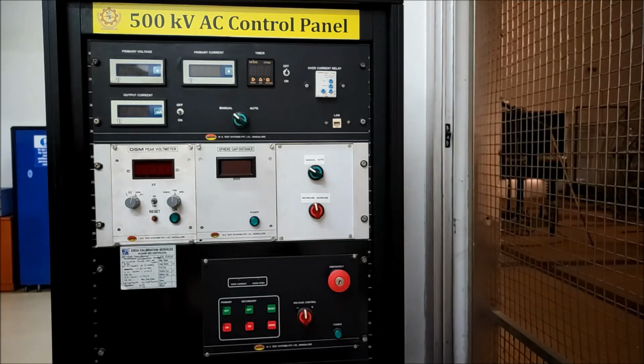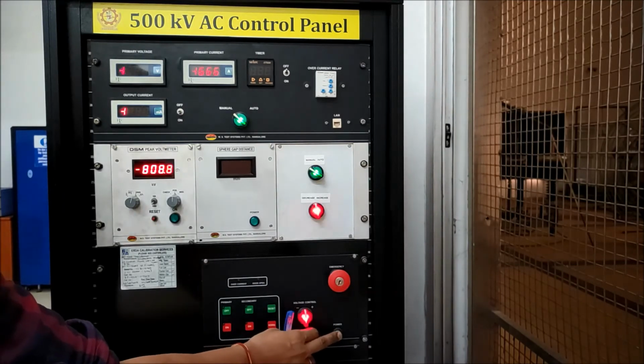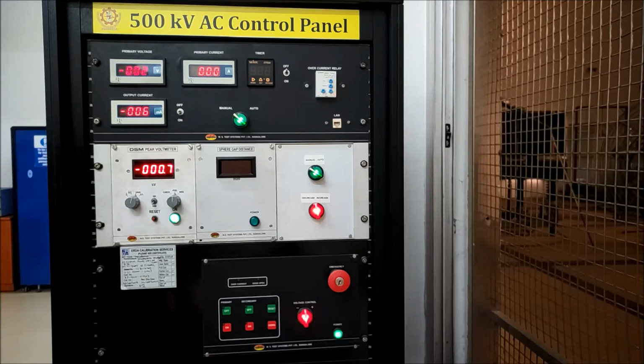Now start our experiment. This is the control panel of the 500 kV AC control panel. This is the power button on the control panel. Now the sphere distance is 1 cm. Okay, then you can increase the voltage across the whole string. At one particular voltage, the sphere will be discharged. Then you can take the reading and calculate.